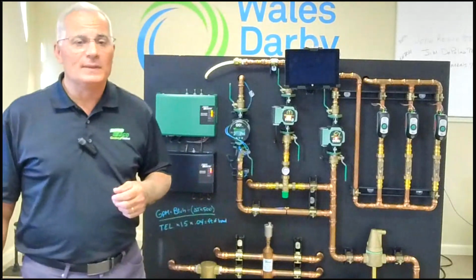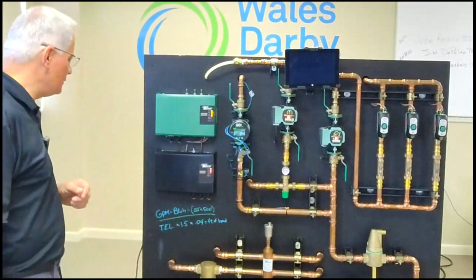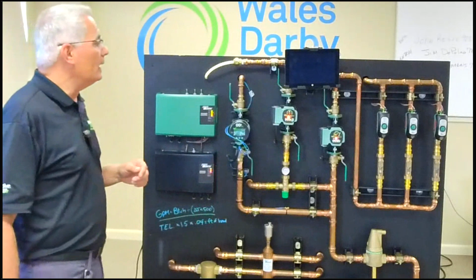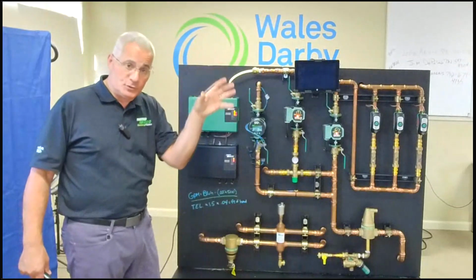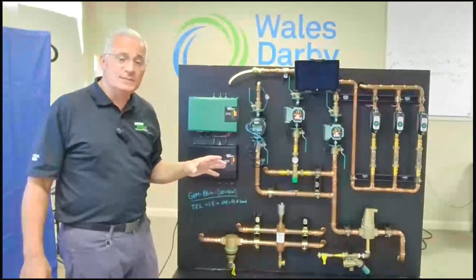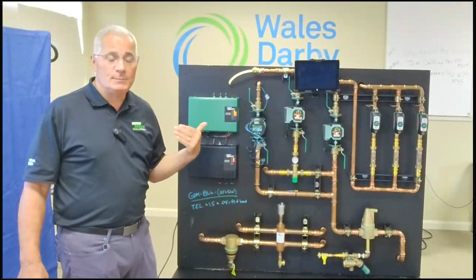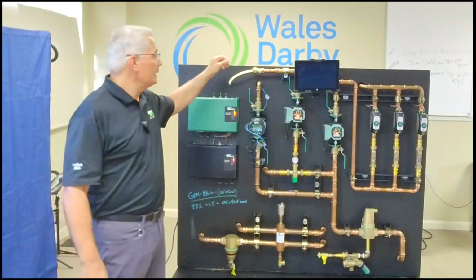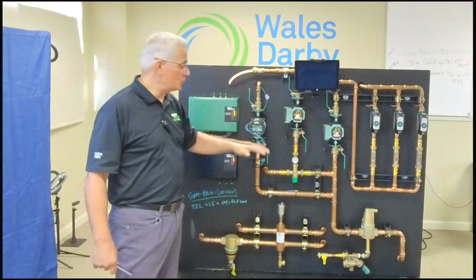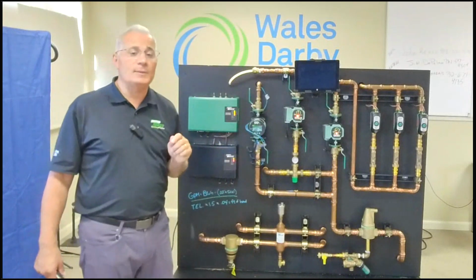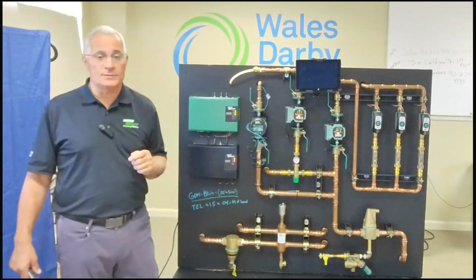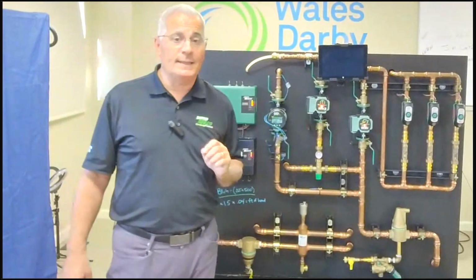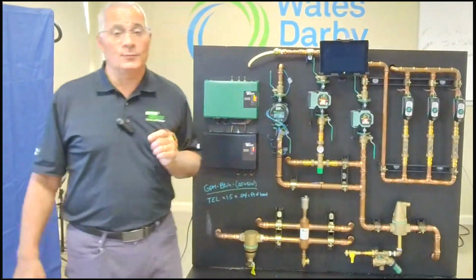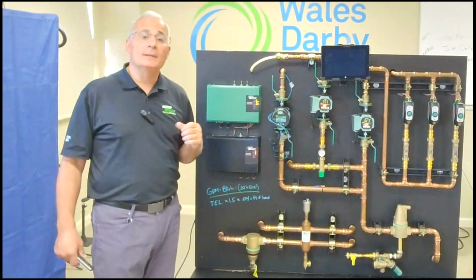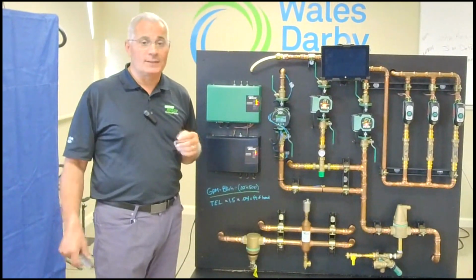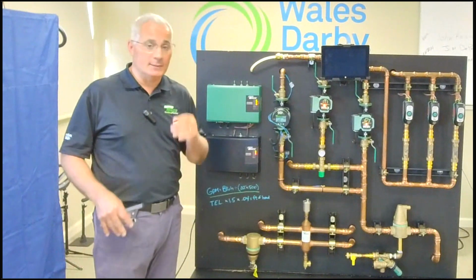You really can't see it because, again, we like to use this as a teaching tool now that we have it. It'll also have a PEX pipe chart right there in the middle, so you can see the head loss per GPM per foot, because the inside diameter of PEX is much smaller than copper. We have to be aware of that when we are sizing our circulators. We cannot go over 4 feet per second, so we really want to make sure that we size things correctly. All that information is right there in the Taco catalog.